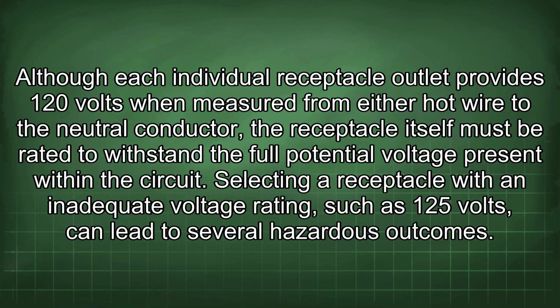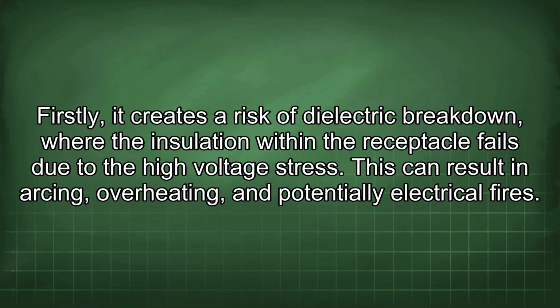Although each individual receptacle outlet provides 120 volts when measured from either hot wire to the neutral conductor, the receptacle itself must be rated to withstand the full potential voltage present within the circuit. Selecting a receptacle with an inadequate voltage rating, such as 125 volts, can lead to several hazardous outcomes. Firstly, it creates a risk of dielectric breakdown, where the insulation within the receptacle fails due to the high voltage stress. This can result in arcing, overheating, and potentially electrical fires.